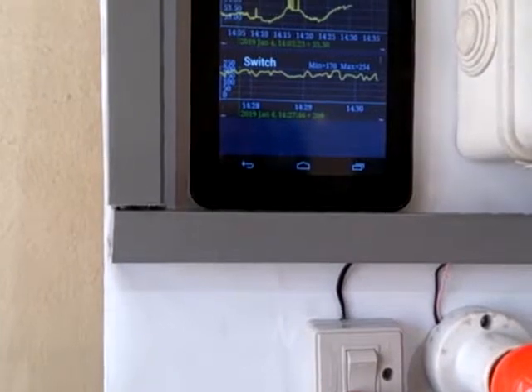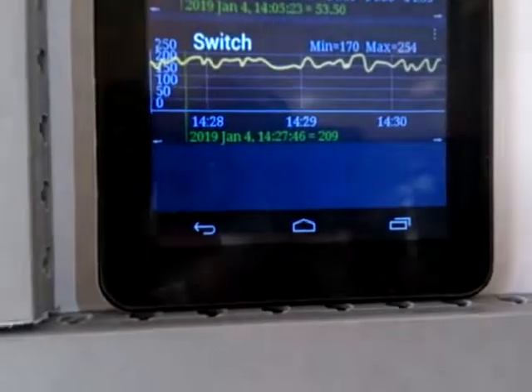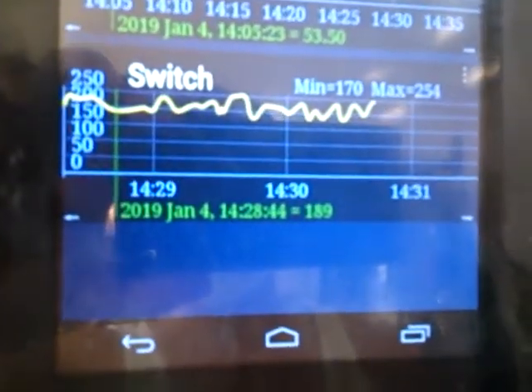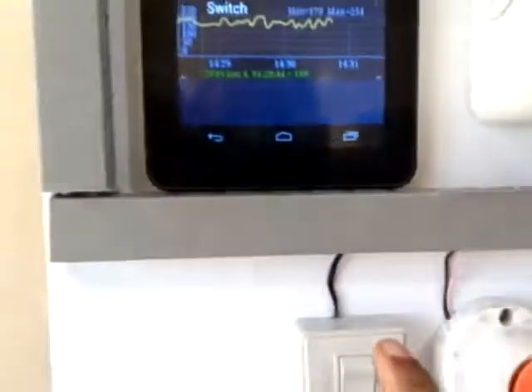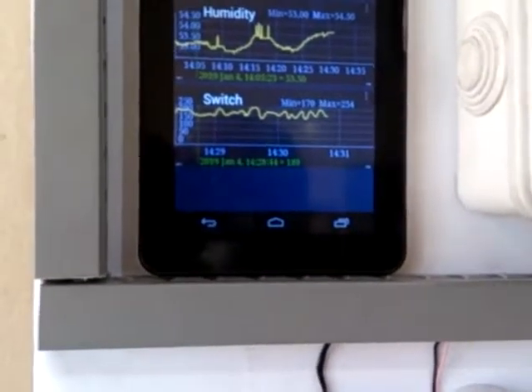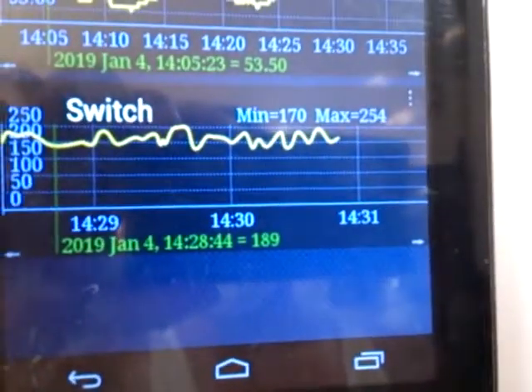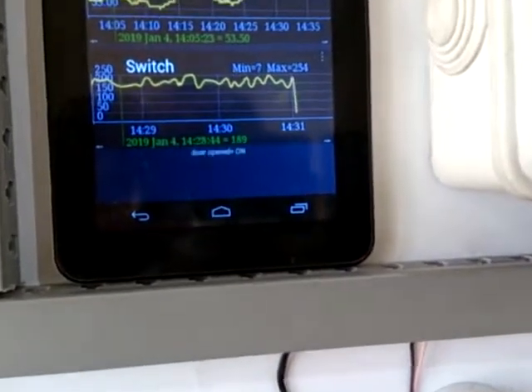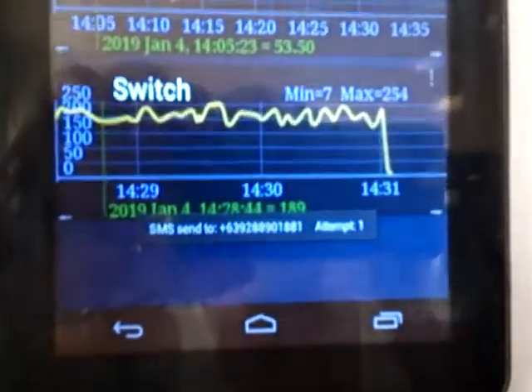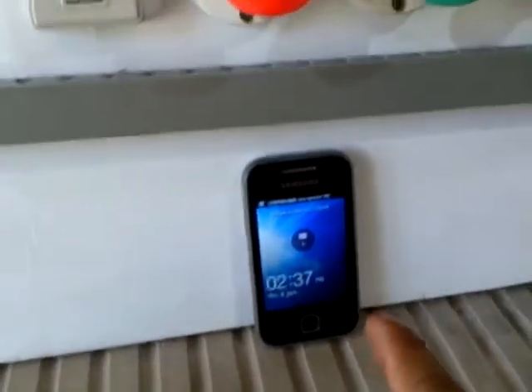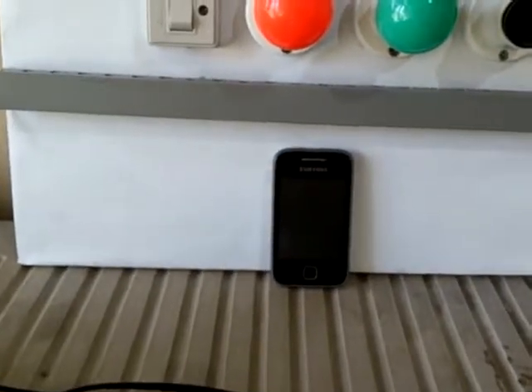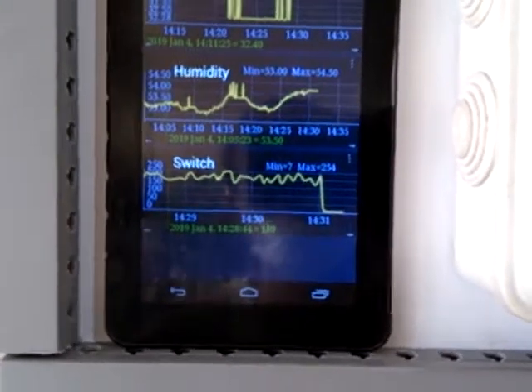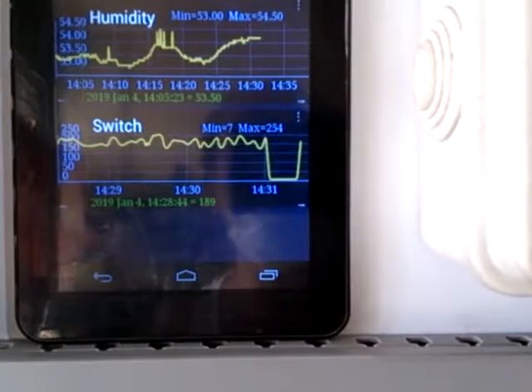The switch below monitors the status of the door switch. If I turn this off, the signal wire floats to a positive value — represented by about 156 on the data — and we see that it is an analog signal that goes up and down. When I turn it on it will pull the data to zero. As we see on the graph, if I switch this one, the graph will reflect the value.